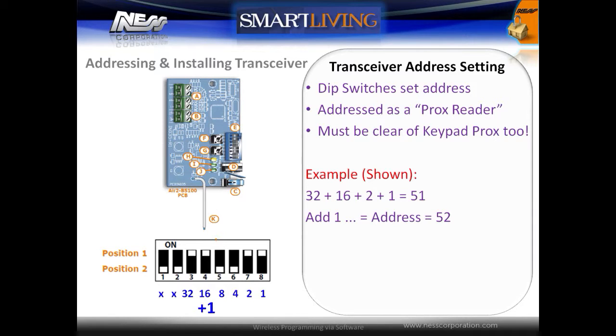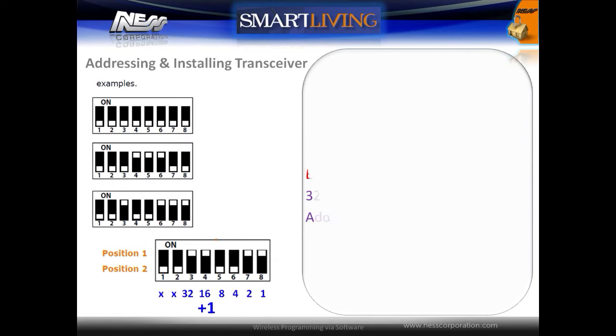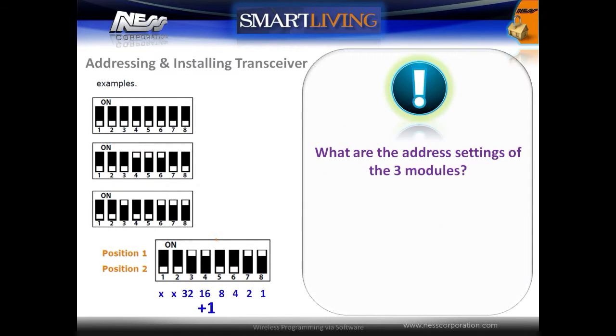In the example shown, we have switches 3, 4, 7 and 8 on. This gives us a total value of 51, and then adding 1 we get the address of 52. Additional information can be found in the tech notes included with every Smart Living panel or in the installation manual on page 34.